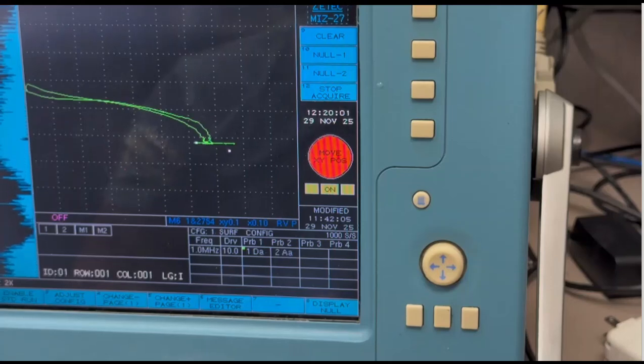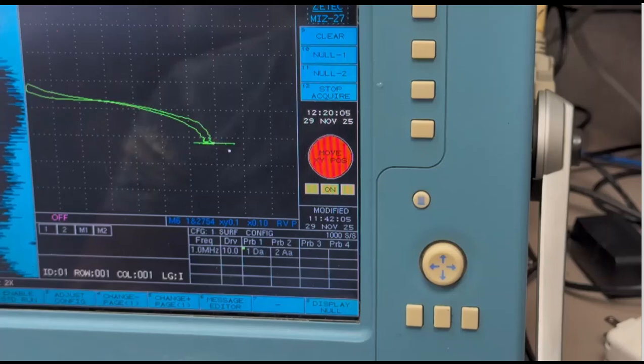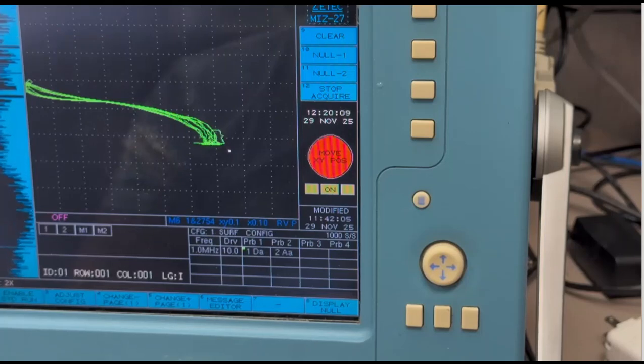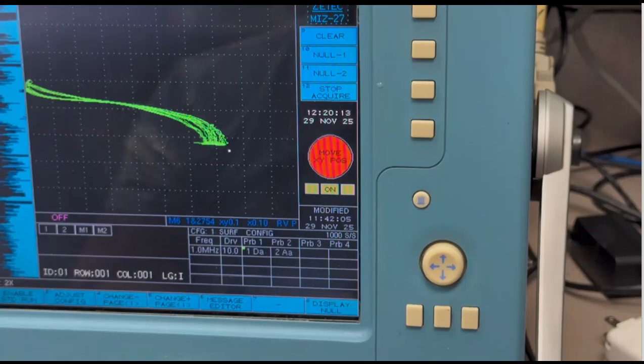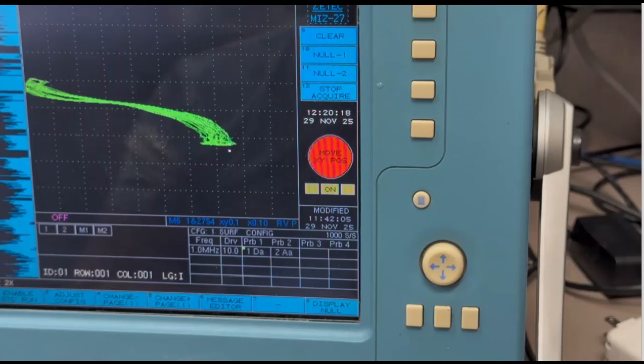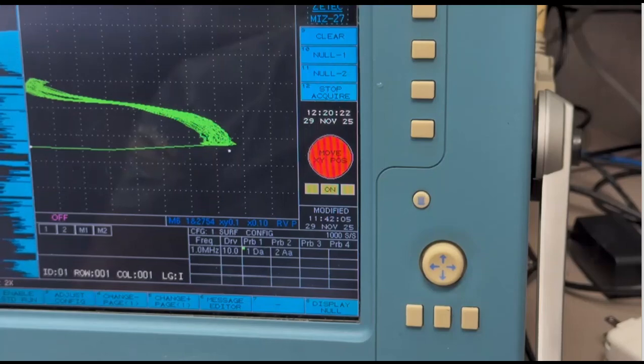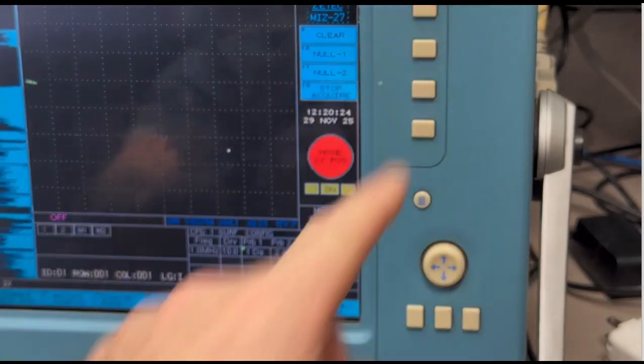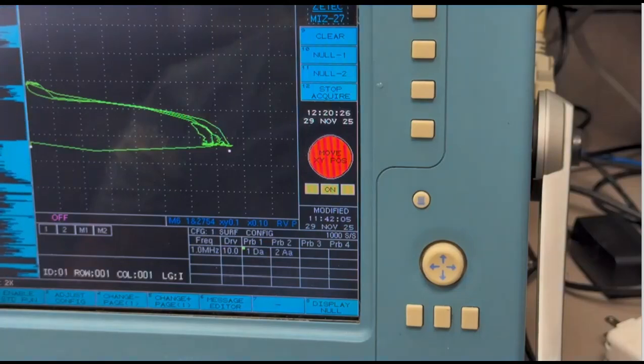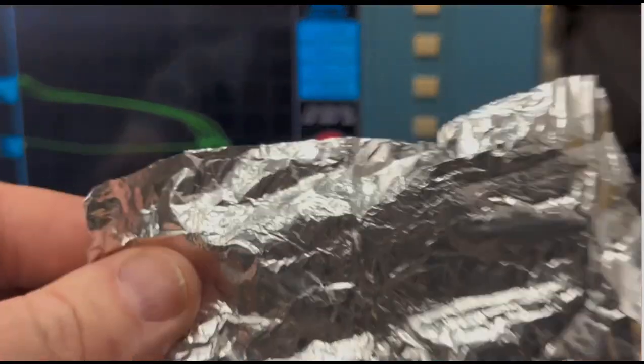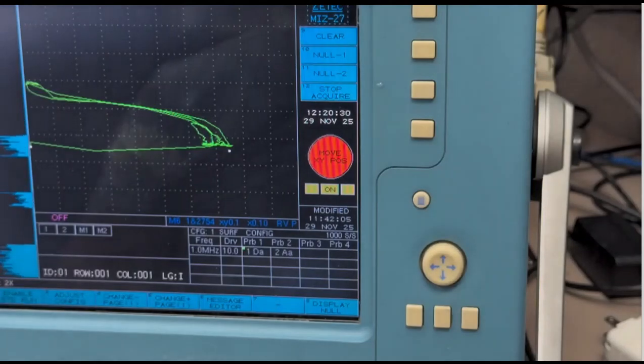So let's just touch this probe down onto the surface. Here's the signal from my deepest EDM notch in the block open to the surface. And that's about 75% of the width of the screen. So it's got a large amplitude. The reason it's large amplitude is because there's a lot of eddy currents being disturbed down to that one millimeter depth.